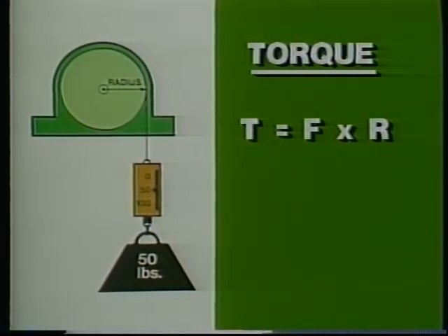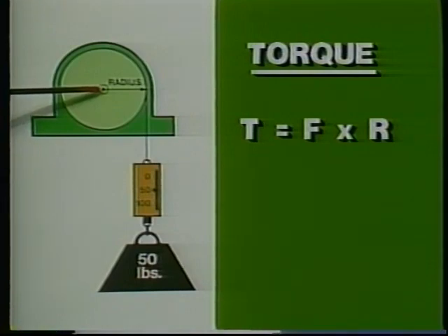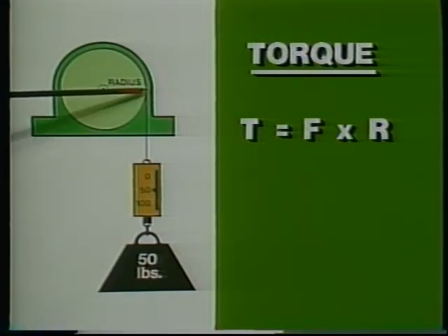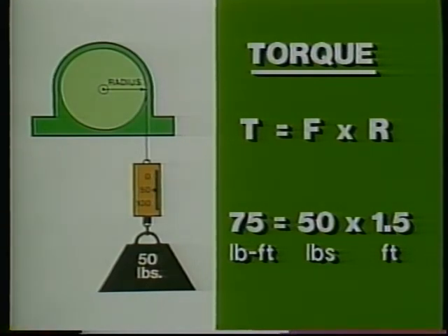The torque a motor produces is measured by multiplying the amount of force it will exert times the distance between the center of the shaft and the point where the force is being applied — in this case, the rim of the winch. If the winch drum is three feet in diameter, its radius is one and a half feet, so the motor must exert 75 pound-feet of torque to raise the load.